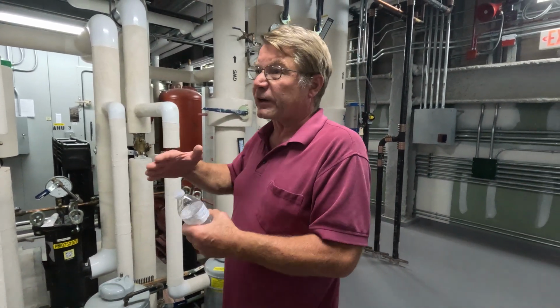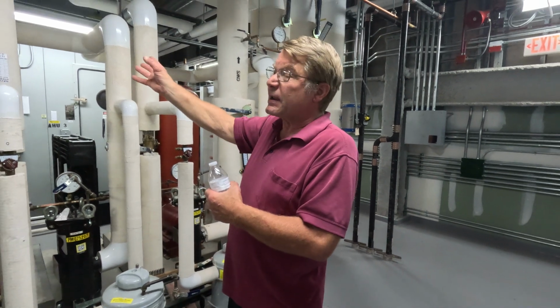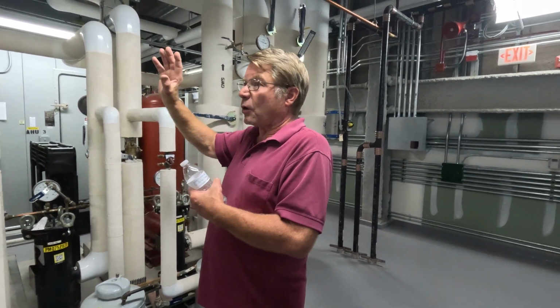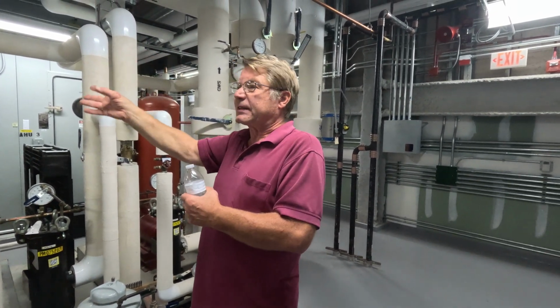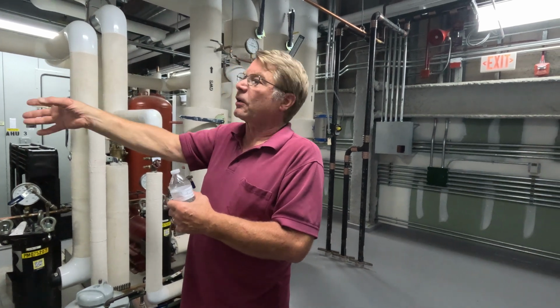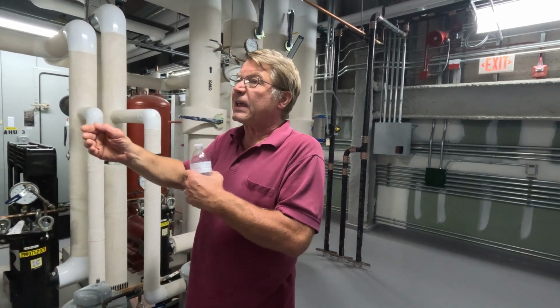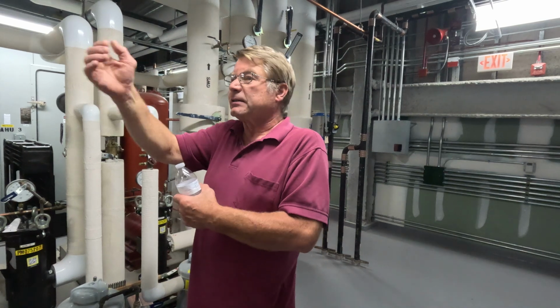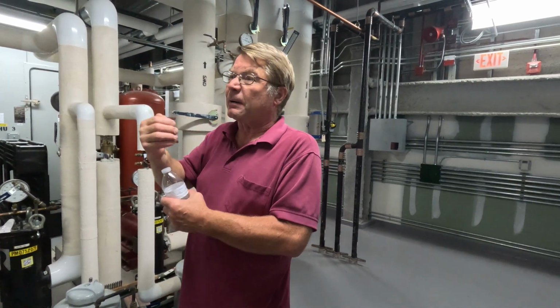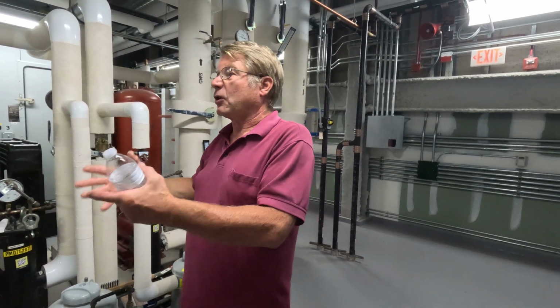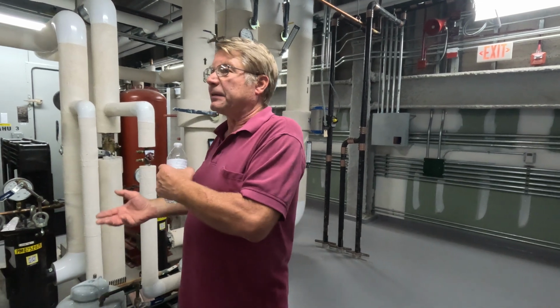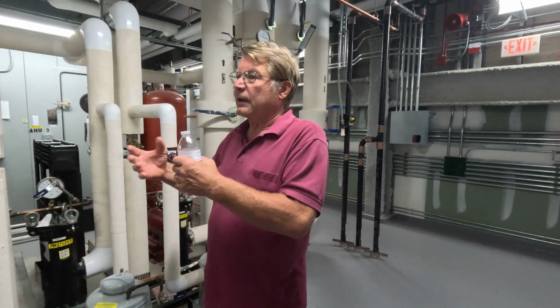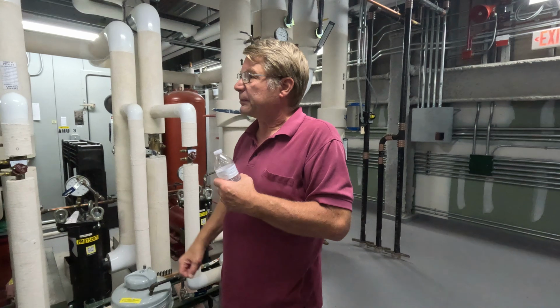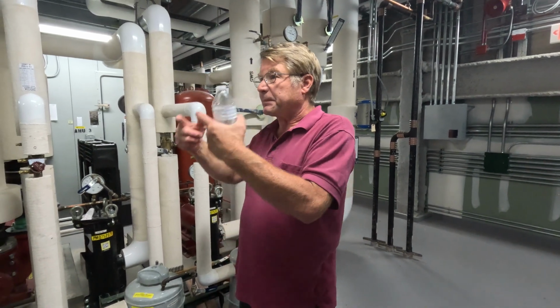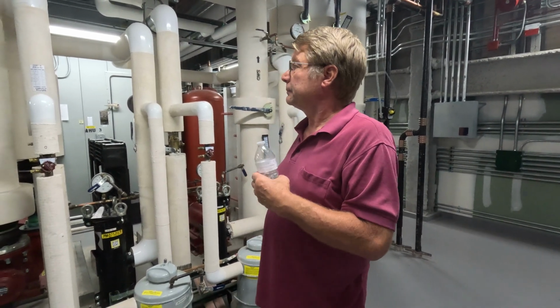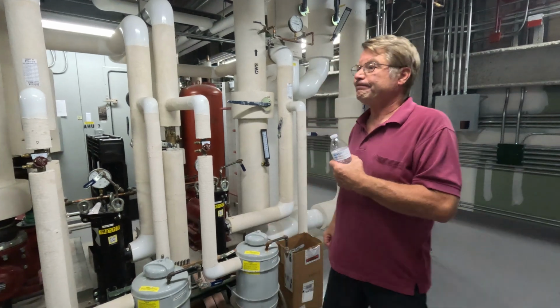In the wintertime, it works the opposite. It takes the 72-degree air going through the coils, transfers that 72 degrees to the glycol. Glycol comes to here. The water's then heated up to 120 degrees to again start to temper that air coming in, the cold air coming in. The cold water then goes back down to the chilled water system, and again they do this recircular, keep the cycle going. Okay? Questions? Okay.